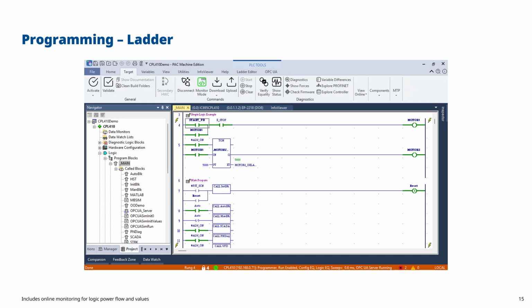And you can see my current sweep time is 0.6 milliseconds, so it's a very fast CPU, this one. And my OPCUA server is running, and I've got 2 faults, and I've also got no warnings. So that's what that status bar is telling me. If I wanted to see the faults, I would double click on the target, which you can now see has a green icon next to it, a green sort of square. That green means we're connected. If I was to double click on that icon there, then that would open up the fault table in the info viewer to enable me to see what's going on with my PLC.